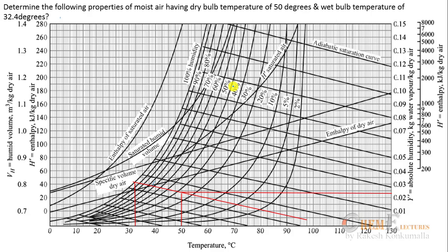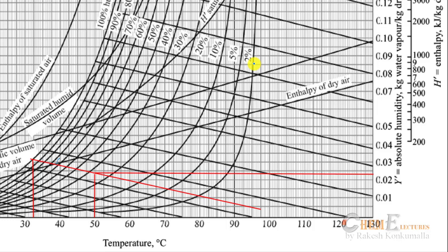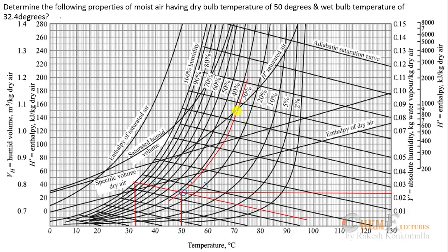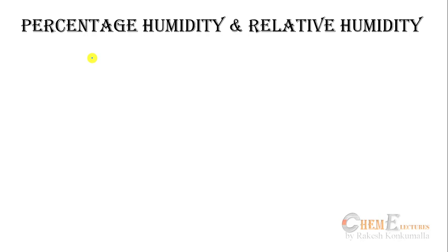Now finding percentage humidity from the chart. The percentage humidity curves range from 2, 5, 10, 20 up to 100%. Our point of intersection lies between the 20% and 30% curves. Drawing a curve parallel to the 30% curve through our point, I can observe that the percentage humidity is approximately 28%.